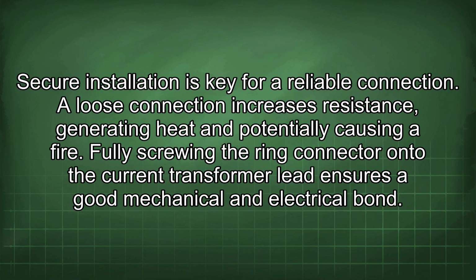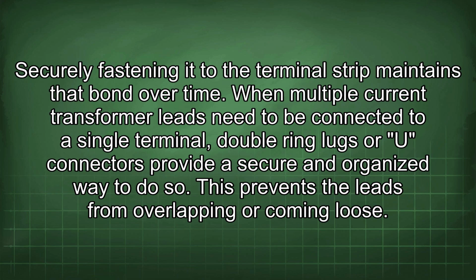Secure installation is key for a reliable connection. A loose connection increases resistance, generating heat and potentially causing a fire. Fully screwing the ring connector onto the current transformer lead ensures a good mechanical and electrical bond. Securely fastening it to the terminal strip maintains that bond over time. When multiple current transformer leads need to be connected to a single terminal, double ring lugs or U-connectors provide a secure and organized way to do so. This prevents the leads from overlapping or coming loose.